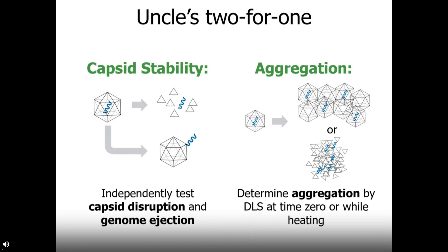Coming back to AAV, UNCLE can deliver two different kinds of stability information: capsid stability and aggregation. For capsid stability, UNCLE uses its fluorescence to measure two different behaviors — protein unfolding and capsid disruption, or genome ejection from mostly intact capsids, sometimes called uncoating. We'll look at data from both the literature and from UNCLE to demonstrate those behaviors. On the aggregation side, UNCLE's SLS and DLS capabilities will identify when aggregation occurs — either at time zero to confirm your sample is monodisperse, or during a thermal ramp as a measure of colloidal stability.